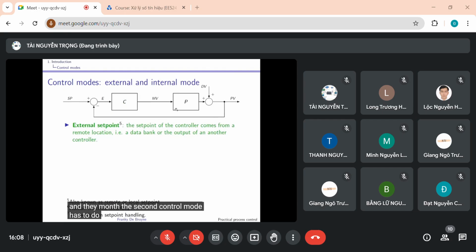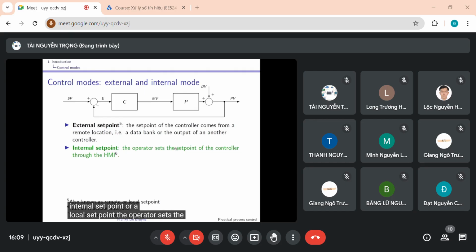The second control mode has to do with the setpoint. So this controller can either be in external setpoint mode or in internal setpoint mode. Sometimes you find other names such as remote setpoint and local setpoint. So external setpoint mode corresponds to remote setpoint mode, and internal setpoint mode corresponds to local setpoint mode. In external mode, we speak about an external set point. This means that the set point of the controller comes from a remote location, from something that is external to the system. For instance, a data bank or the output of another controller, and this is the case, for instance, in a cascade. In internal mode, we speak about an internal set point or a local set point. The operator sets the set point of the controller directly through the human-machine interface.